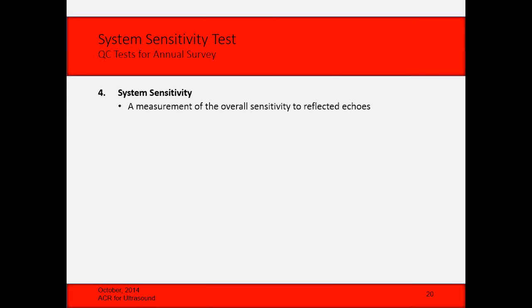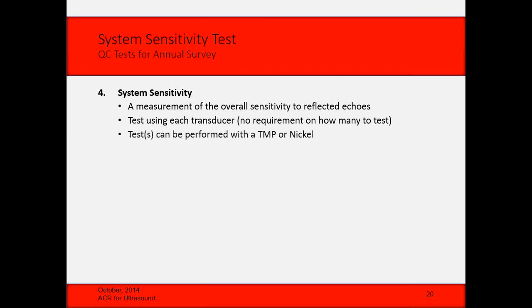System sensitivity, so that's a measurement of the overall sensitivity to reflected echoes. I say do this test using each transducer, but there is no requirement. The ACR used to say you had to test 2 probes at least. There's actually no requirement now for that. So this is Jim Carr saying I would test every transducer that they use. You know, they'll find transducers in drawers they never used. I wouldn't necessarily do that, but anything they're using, you should really test that. You can do that with a tissue mimicking phantom or the nickel.